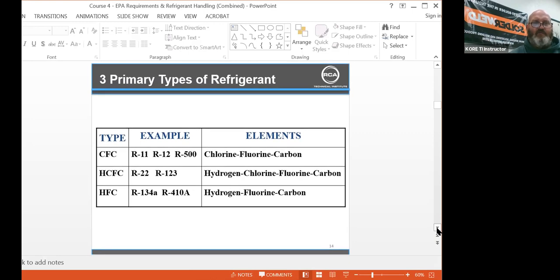Three types of primary refrigerant is a CFC: R11, R12, R500, 502, 503, 507. Those are high CFCs. And HCFC is R22 and 123. And HFC is 134A, 410, and 404. Again, 134A, 410, this was done about 4 years ago. We know that R410 and 404A are on the hit list to be gone.